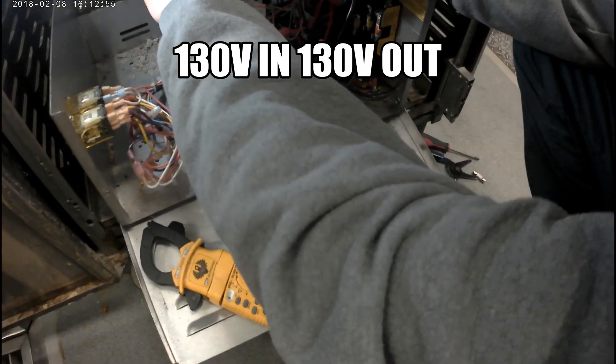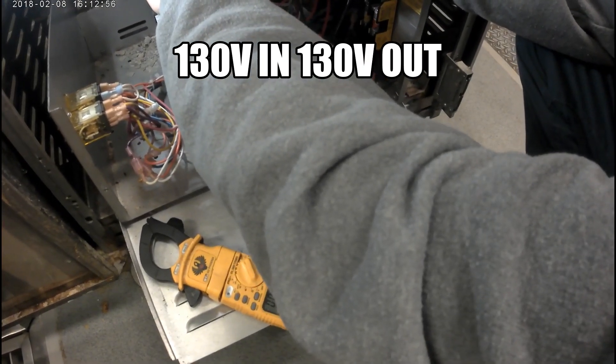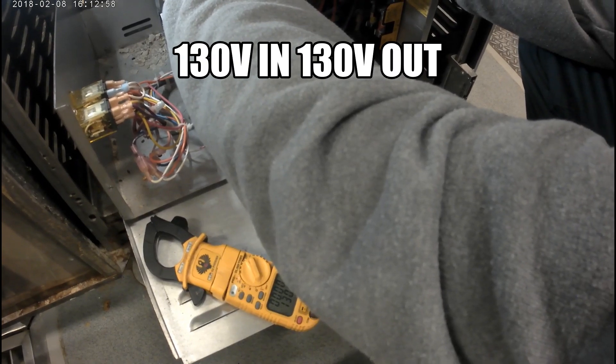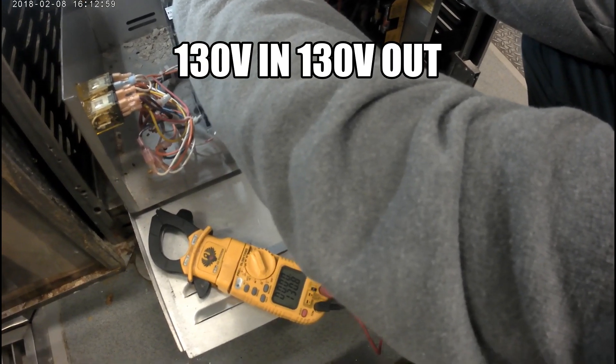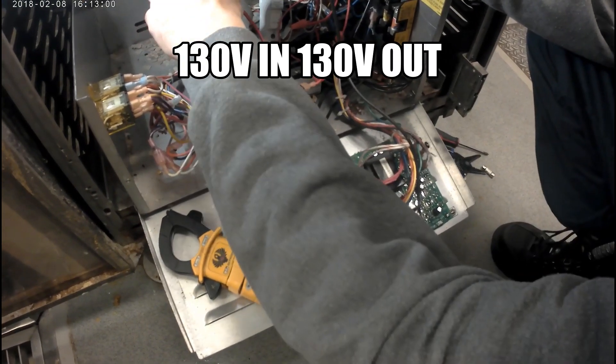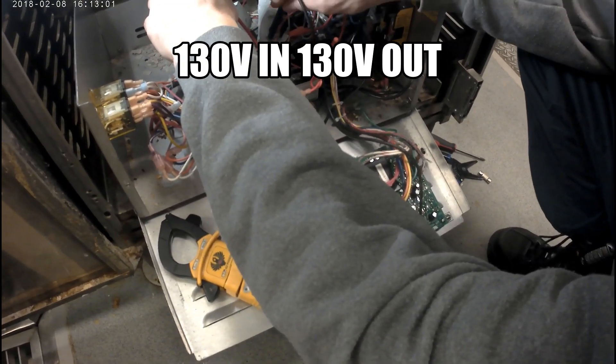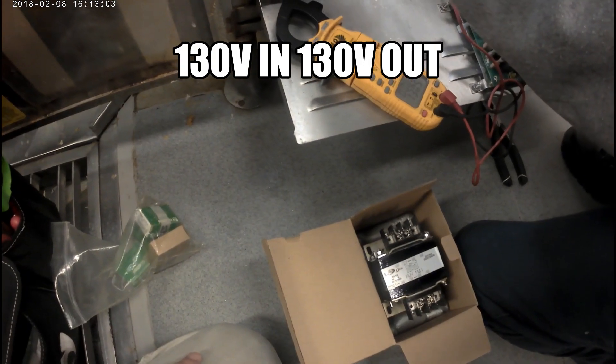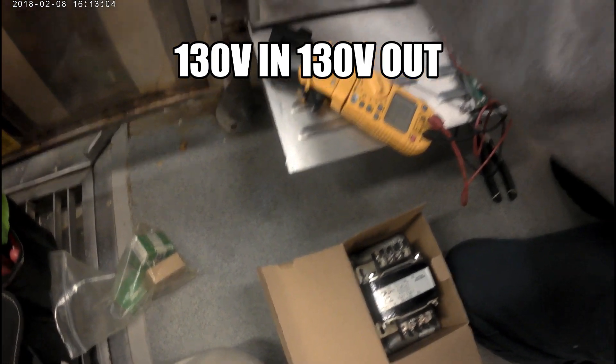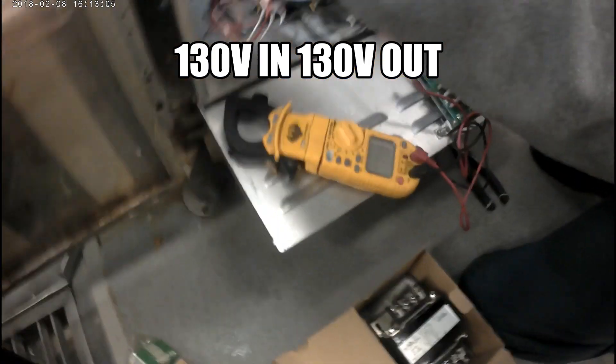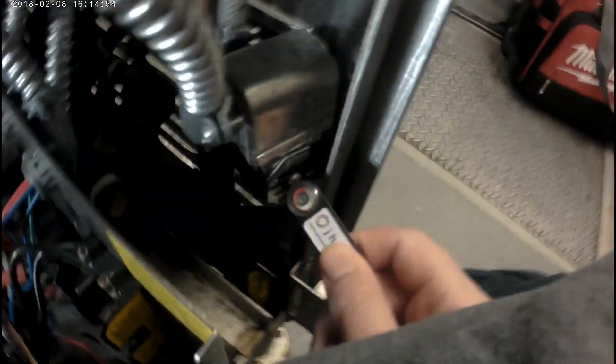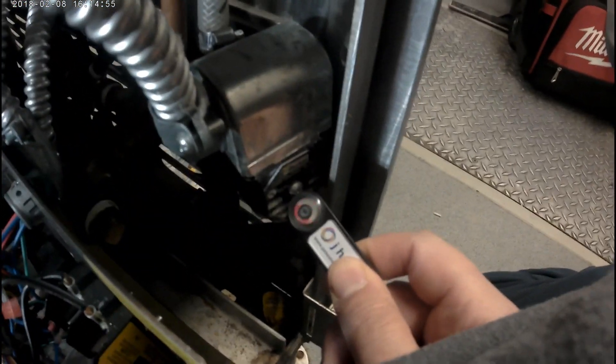Right now I have the drain valve disconnected, I have 130 volts into my fuses, 130 volts out of my fuses. Unit's running for more than two seconds, which is a huge improvement. You can see my fill solenoid is running, we have power there.